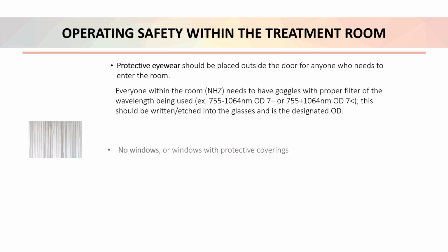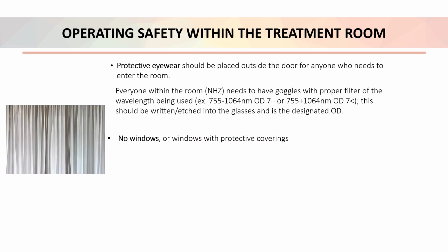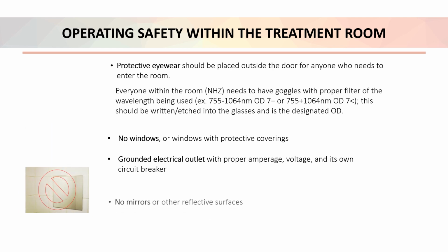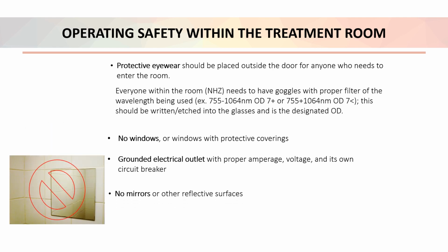Optimally, there should be no windows in the treatment area, or at least, windows with protective, non-reflective coverings. There should be a grounded electrical outlet with proper amperage and voltage ratings for your specific laser, with its own dedicated circuit breaker. There should be no mirrors or reflective surfaces in the treatment area. This would include any personal attire items or other objects that may errantly reflect the light of the laser and become a safety hazard for the technician or patient.